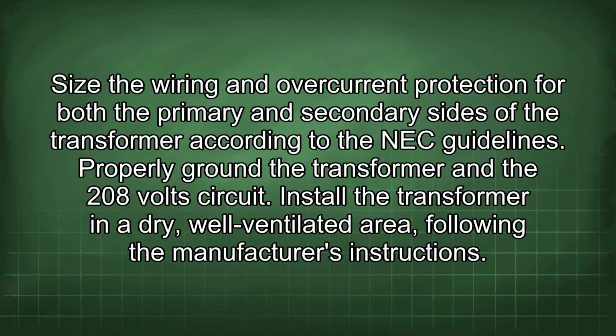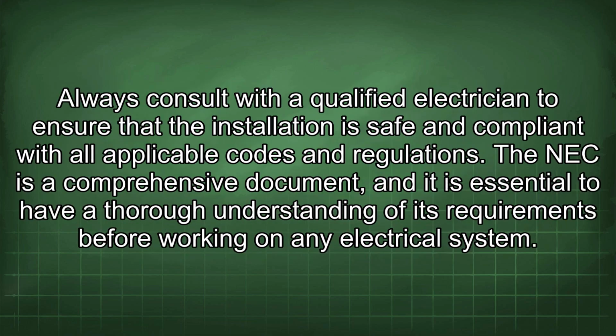Size the wiring and overcurrent protection for both the primary and secondary sides of the transformer according to the NEC guidelines. Properly ground the transformer and the 208 volt circuit. Install the transformer in a dry, well-ventilated area, following the manufacturer's instructions. Always consult with a qualified electrician to ensure that the installation is safe and compliant with all applicable codes and regulations.